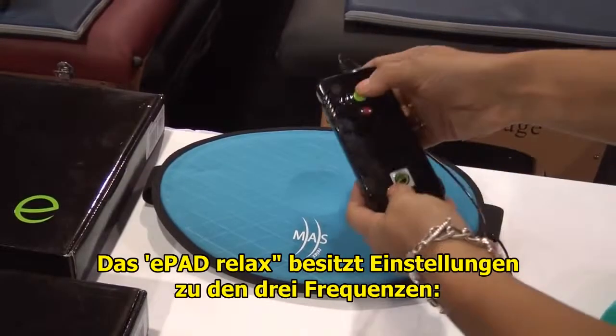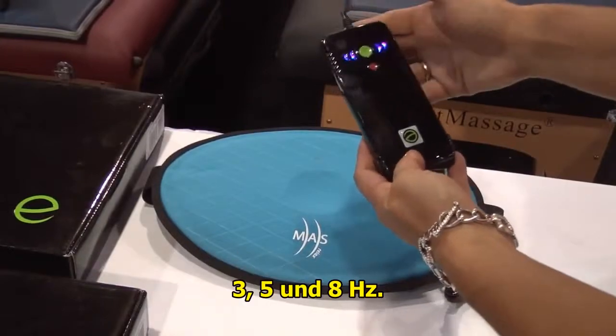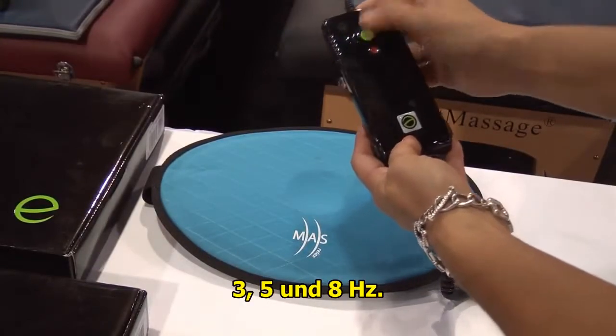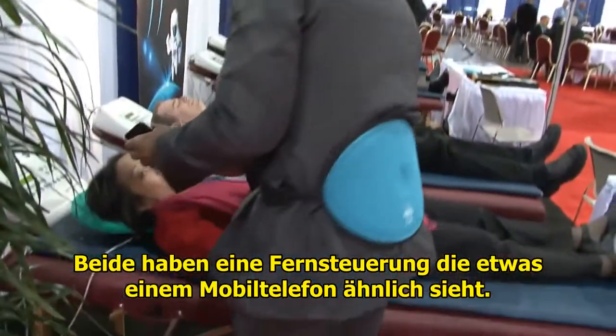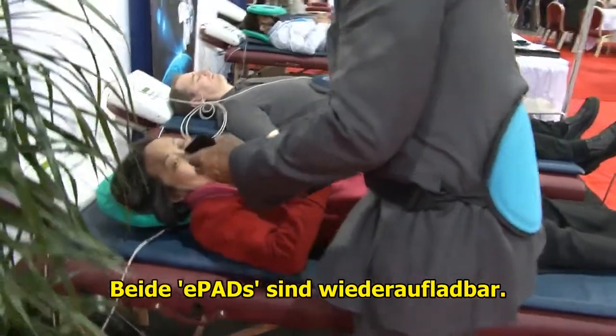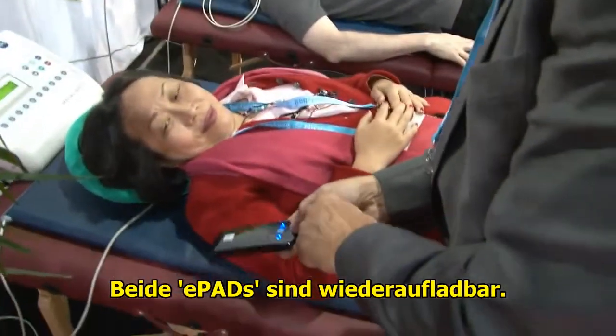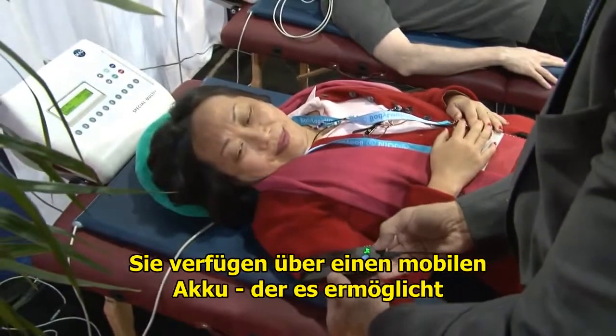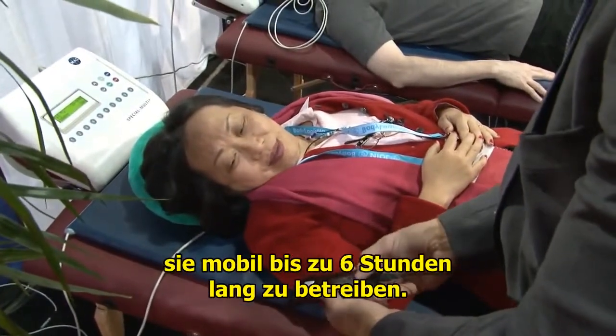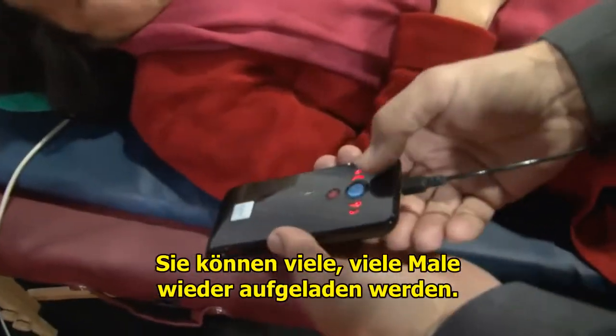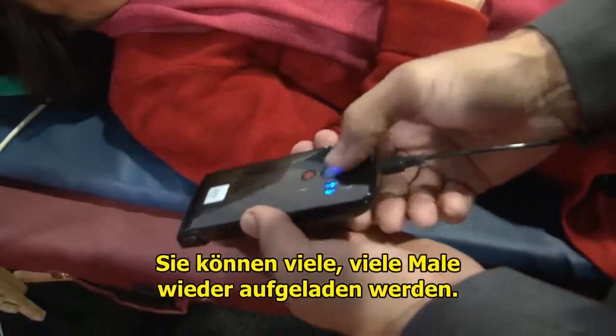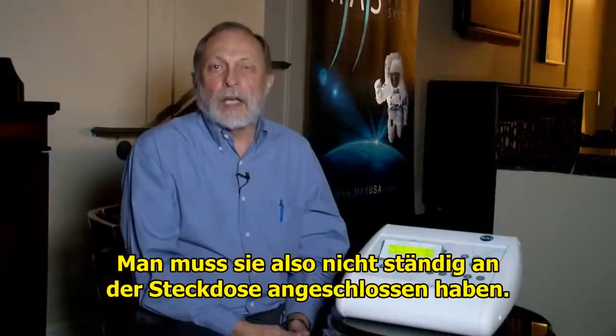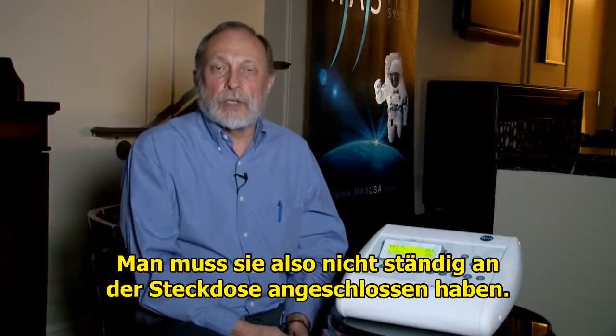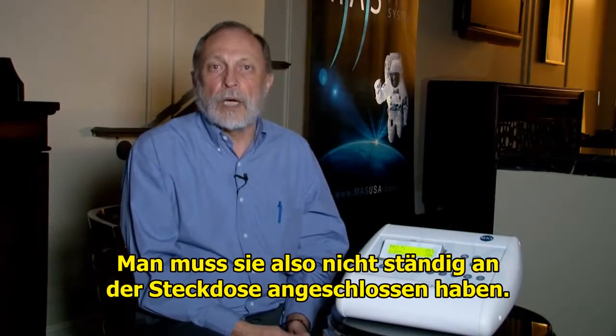The ePad Relax has 3 frequencies, 3, 5, and 8. They have a control unit that looks like a slightly extended iPod. The ePads are rechargeable. They have a portable battery that allows you to have operation for upwards of 6 hours. So they can be recharged and recharged multiple times. Again, allowing for more portability, so you don't have to have it attached to a wall outlet.